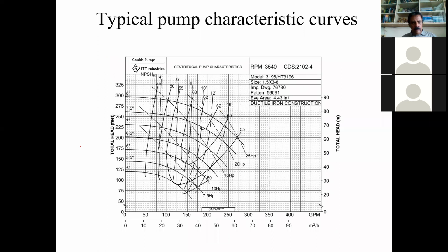So there are several pump sizes available. Normally the manufacturer, for a typical casing, will put several impellers. Like here you have an 8-inch impeller, 7 point something, the same casing, different sizes of impellers provided to make it big or small. As you can see, they're all parallel to each other. In this case, these are the pump characteristic curves, and these are the ISO efficiency curves, which tell you whether your requirement can be met by a very efficient pump from this family of pump curves.